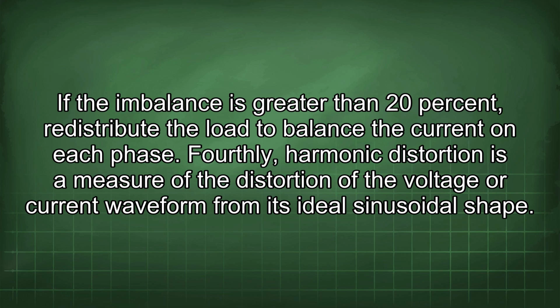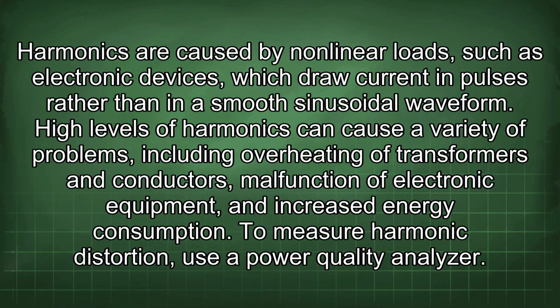Fourthly, harmonic distortion is a measure of the distortion of the voltage or current waveform from its ideal sinusoidal shape. Harmonics are caused by nonlinear loads, such as electronic devices, which draw current in pulses rather than a smooth sinusoidal waveform. High levels of harmonics can cause a variety of problems, including overheating of transformers and conductors, malfunction of electronic equipment, and increased energy consumption.